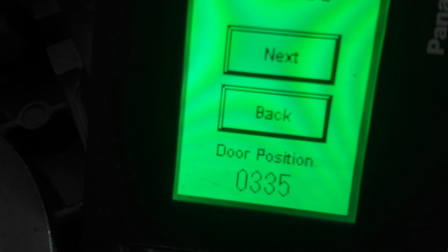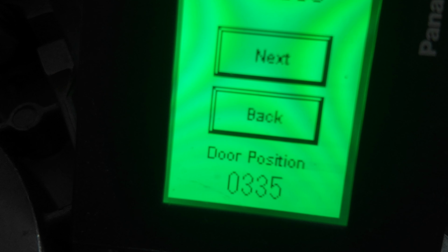In the rare case that all of the above check out and the door position is still reading sporadically, has dead spots during opening or closing cycles, or exhibits large value spikes, then it's possible that the wiper inside the transducer is damaged and the part will need to be replaced.